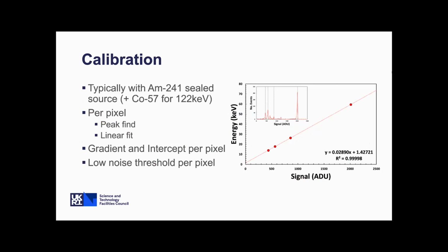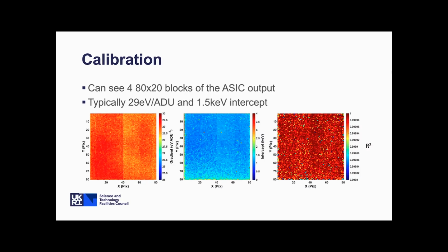When we look at that as an image, you see that we typically have around 29 eV per ADU as a conversion factor, and we have an intercept of around 1.5 keV. You can see in here the structure of those 20 by 80 blocks in the raw data. That's just because each of those blocks is going through a different readout chain. Then the intercepts are here, and this is just showing the correctness of the fit. Those calibration values would be supplied with the detector, so it's not something you'd need to worry about, but it's relatively easy for people to recalibrate in situ as well.